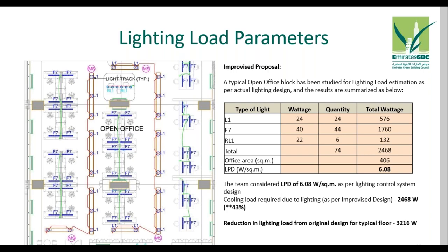Just imagine the building with a complete glass facade. We have enough natural light. 90.1 also talks about controls with occupancy. When people walk in, the occupancy sensors turn the lights on. If the zones are bigger than 600 square feet, then we need to have manual lighting switches to avoid any wastage of lighting. So applying all these things, the lighting load estimates will certainly come down as a design part. And further, if you do energy modeling, those aspects will further improve the energy consumption.